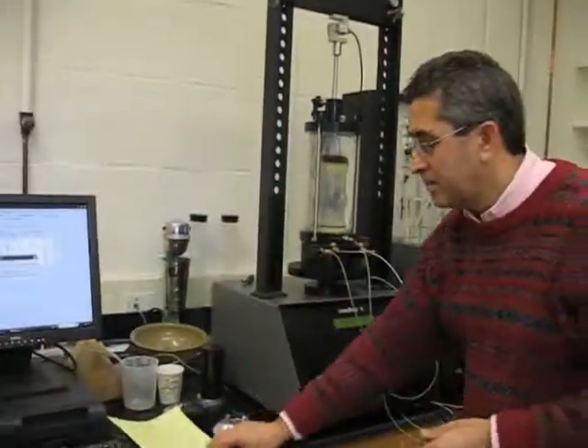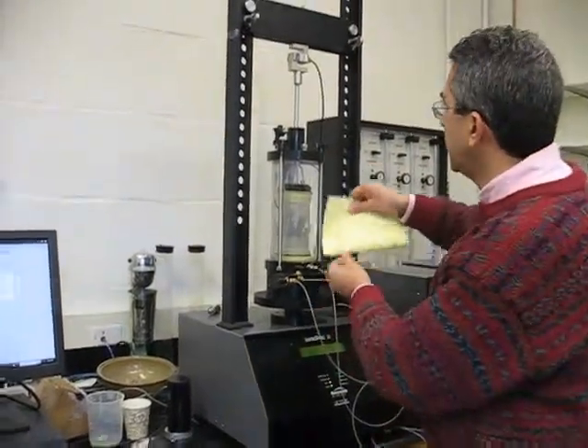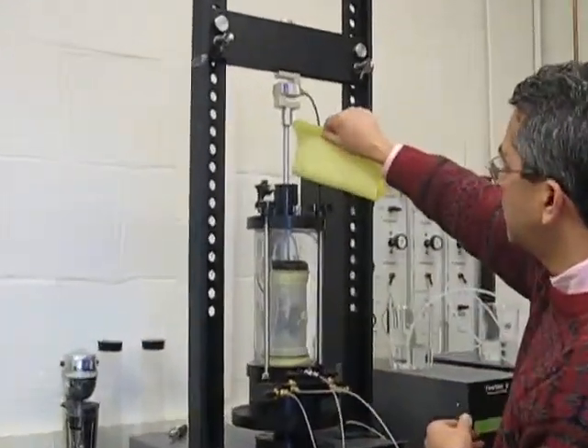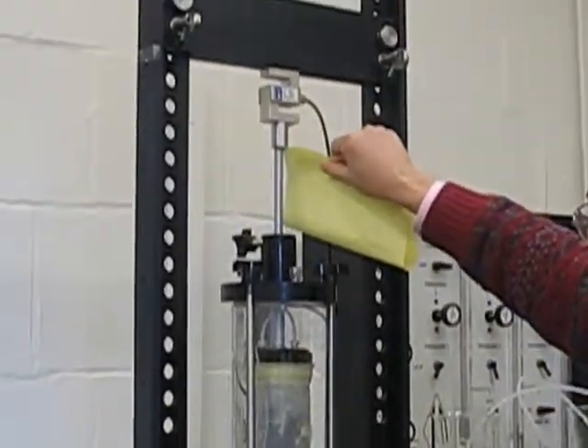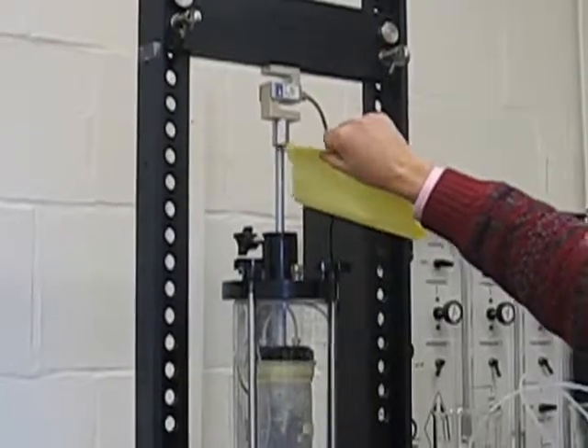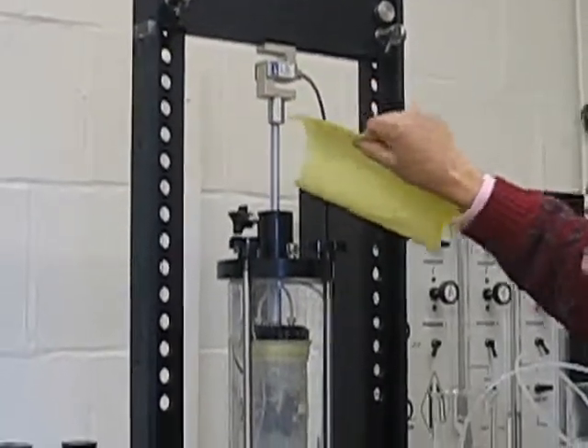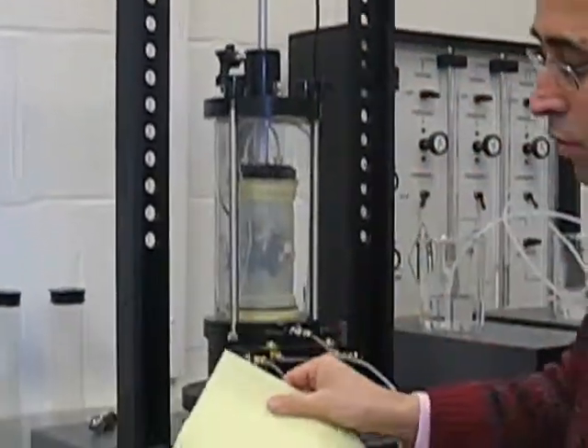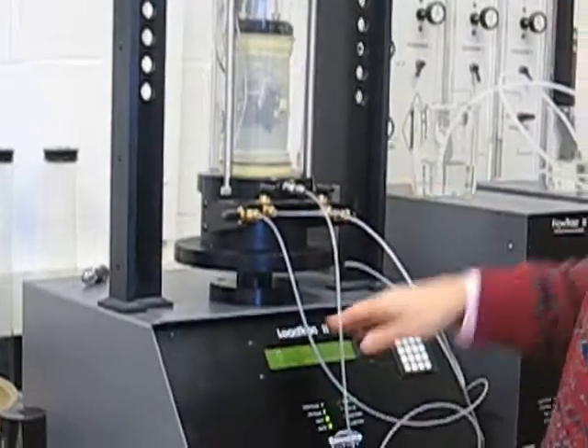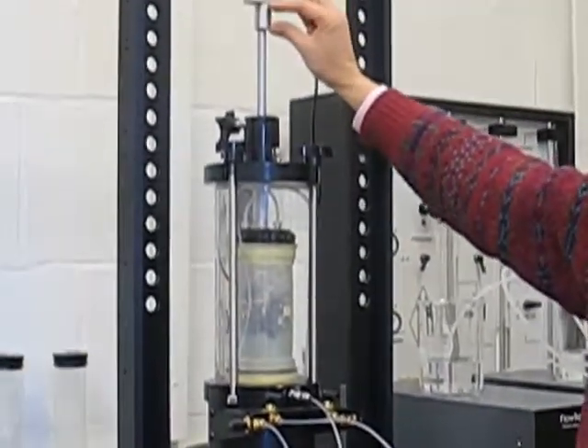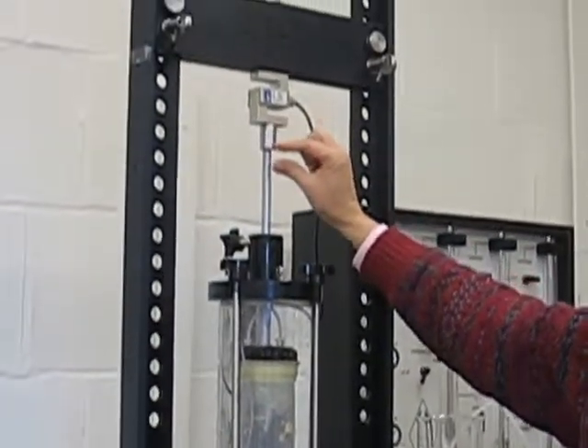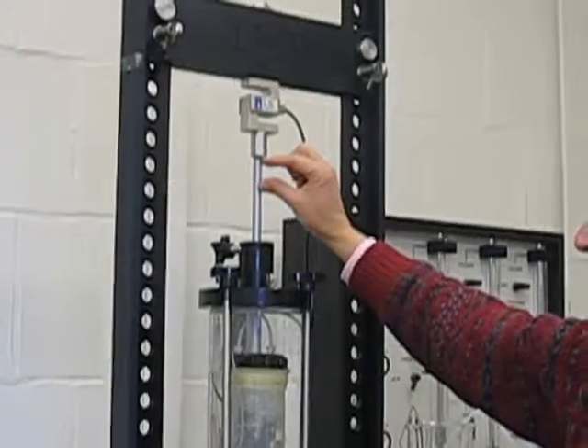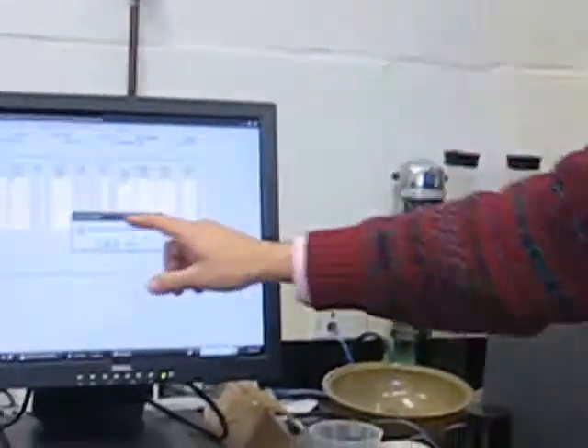Now after the gap is closed, we can check it manually by trying to insert a piece of paper - it should not fit. And typically we put about a quarter pound of load to make contact between the load cell, the button, and the piston.